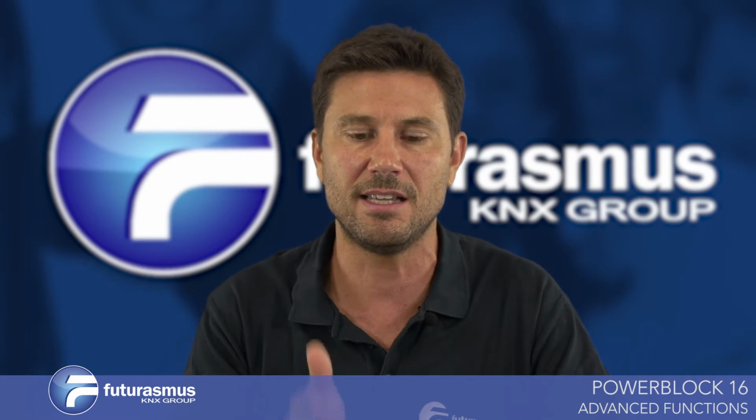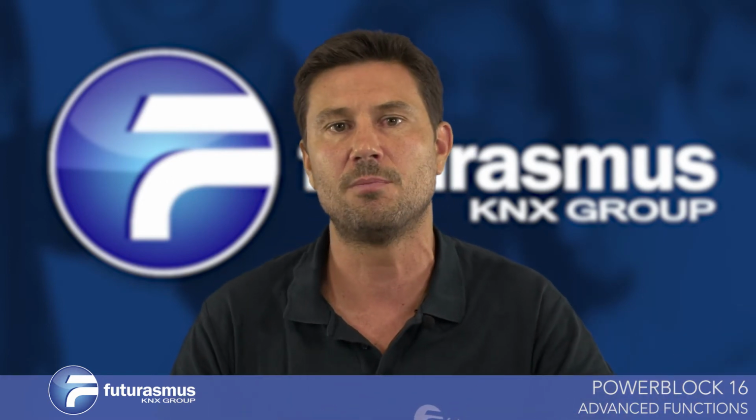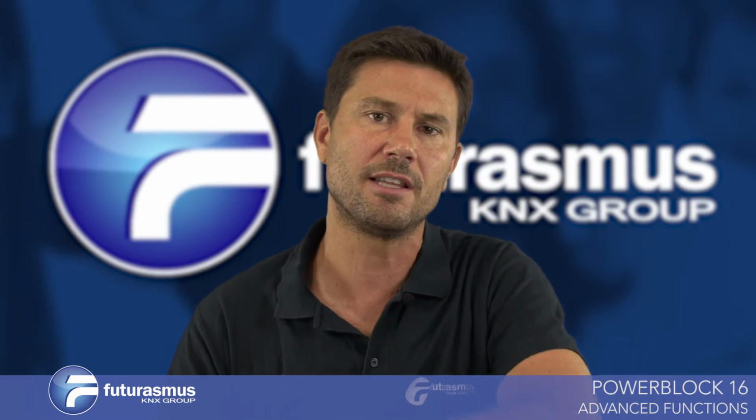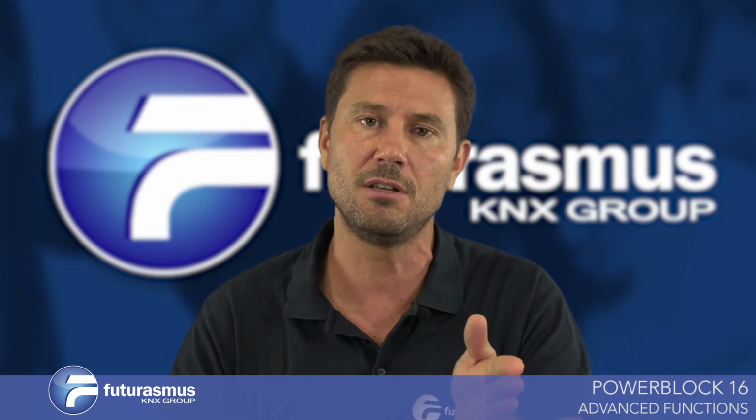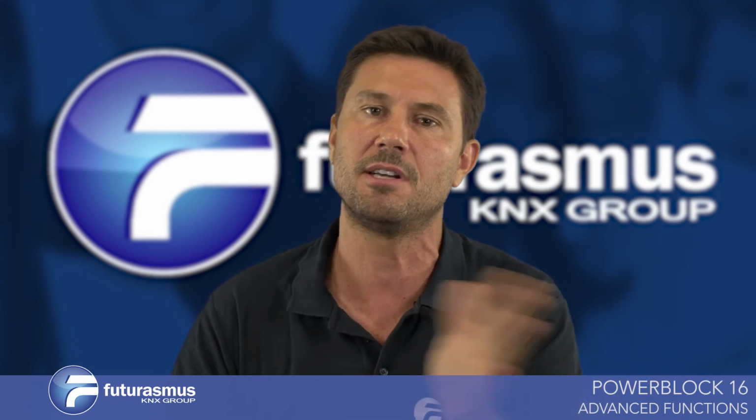Now here in the PowerBlock, you have the possibility to set it individually or totally. You can say what should happen if I download the application program: override all the end user parameters, don't override any of the end user parameters, or do it individually. And if you say do it individually, you can even say which scene numbers you don't want to override, and the rest you should override.